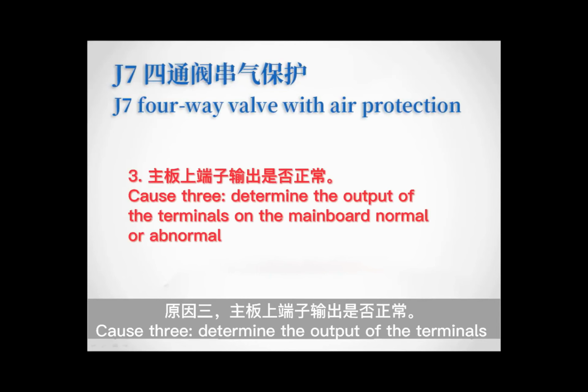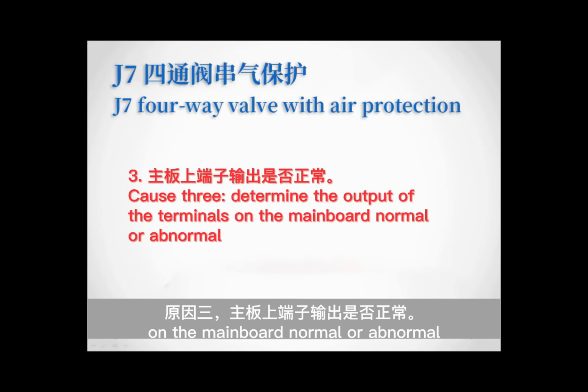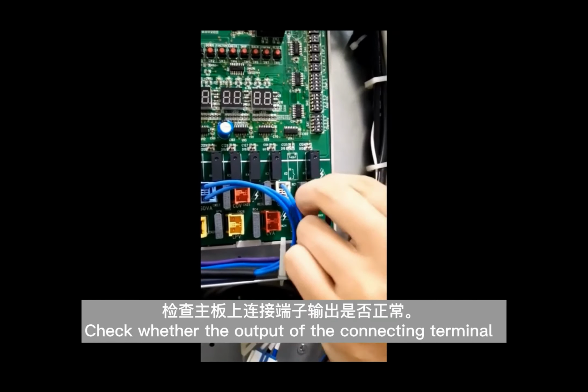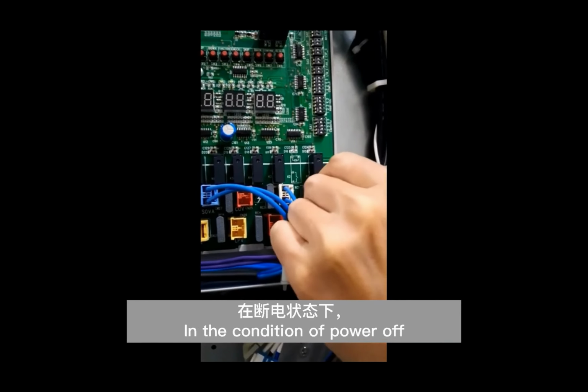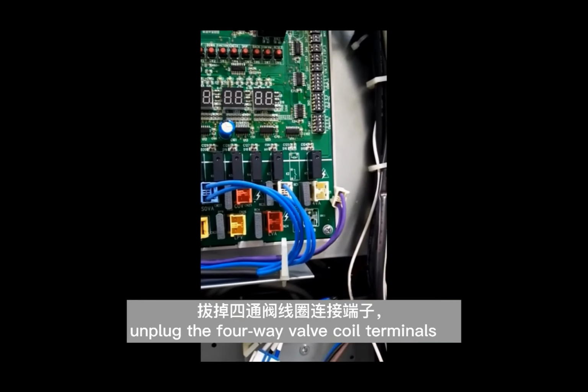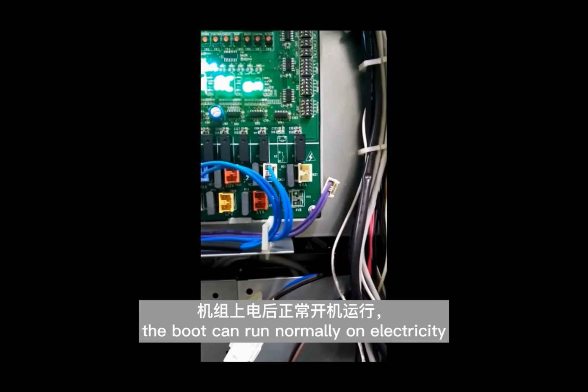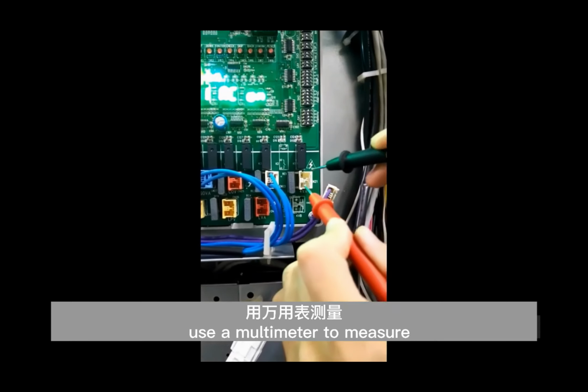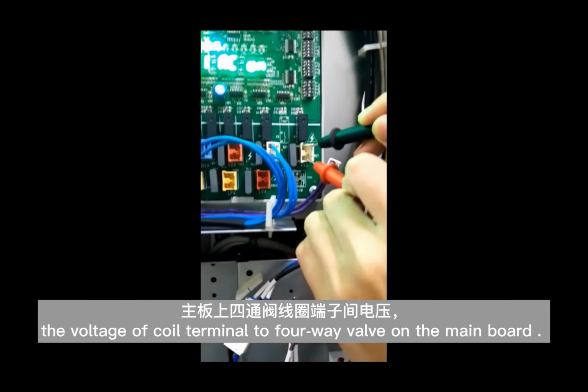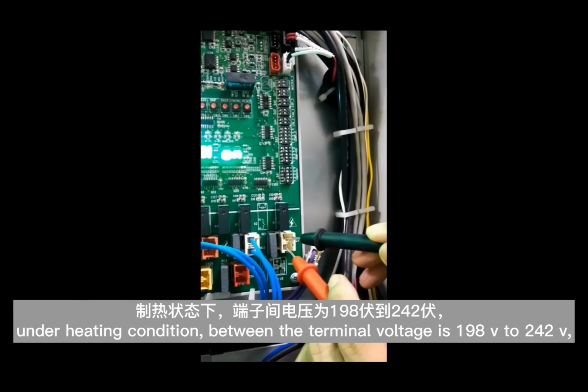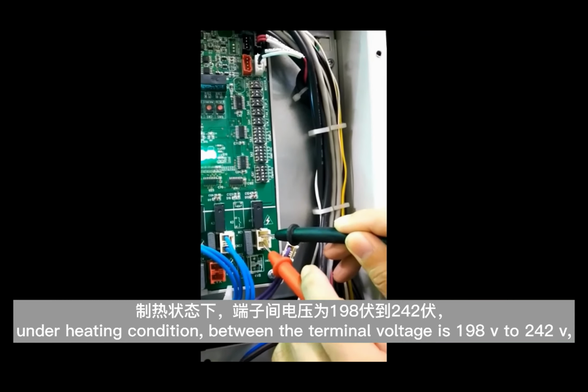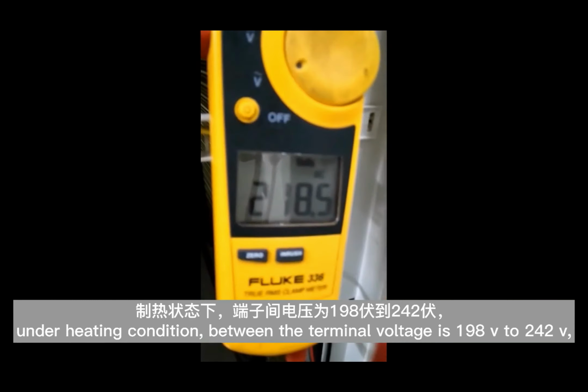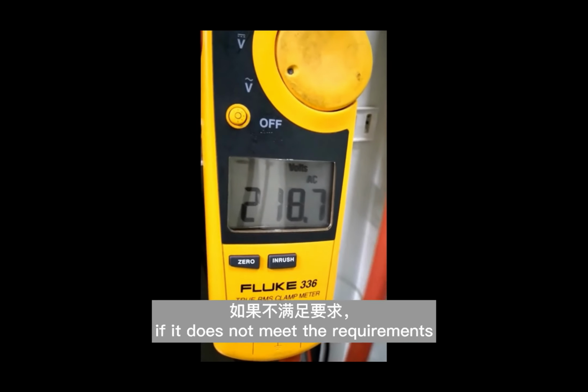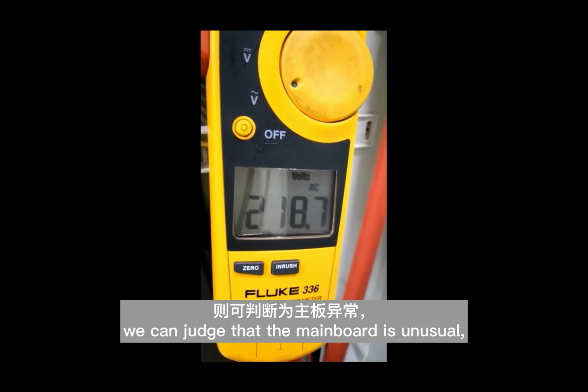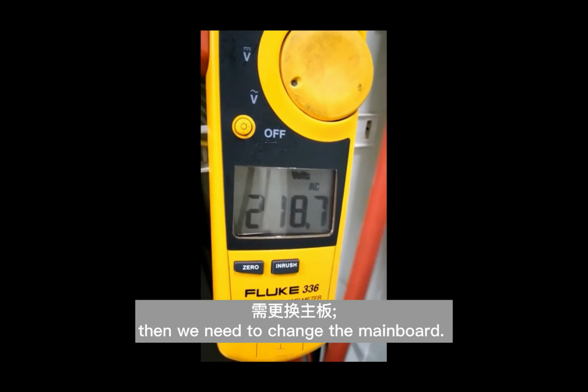Reason 3. Determine whether the output of the terminals on the main board is normal or abnormal. Check whether the output of the connecting terminal on the main board is normal. In the condition of power off, unplug the four-way valve coil terminals. The unit can boot and run normally on electricity. Use a multimeter to measure the voltage of the coil terminal to the four-way valve on the main board. Under cooling condition, there is no voltage between terminals. Under heating condition, the terminal voltage is 198 volts to 242 volts. If it does not meet the requirements, we can judge that the main board is unusual, then we need to change the main board.